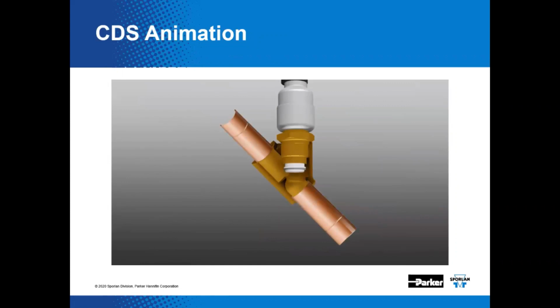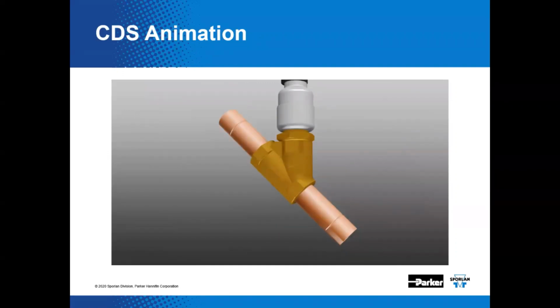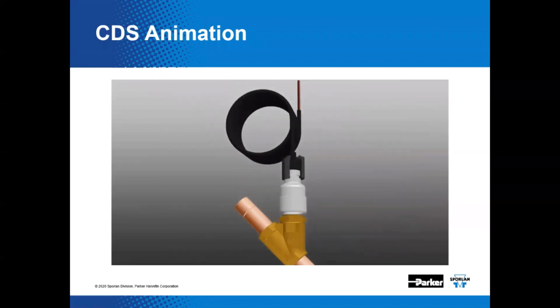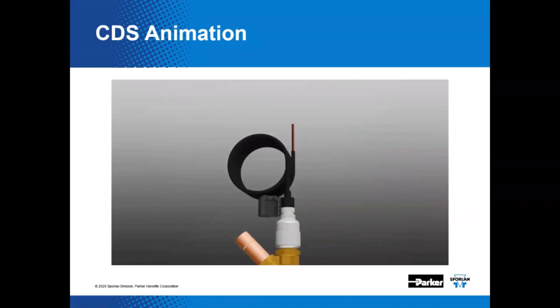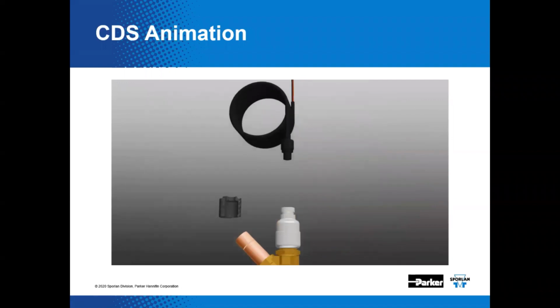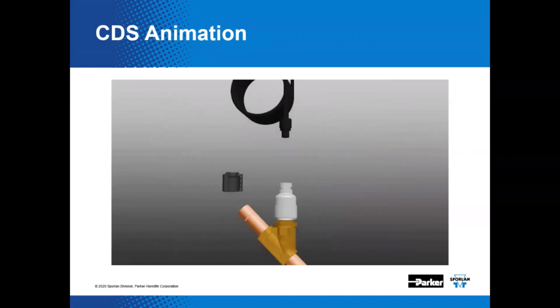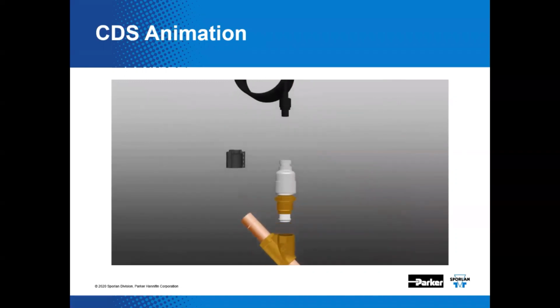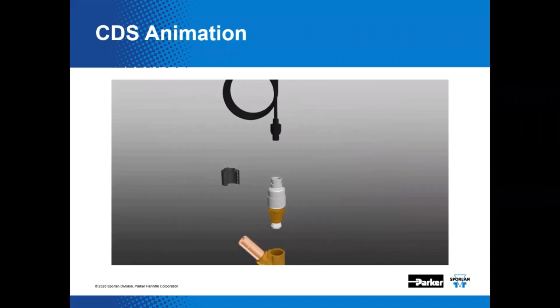Now, replacement motors are available for this product, and you can find all the parts for these valves in our Bulletin 122, which you can find on the Sporlan.com website under literature. Replacement motors are shipped with the piston at mid-stroke. You'll see this motor assembly come off and separate. If power is applied to the motor prior to reassembly, be sure that piston has been retracted before installation.